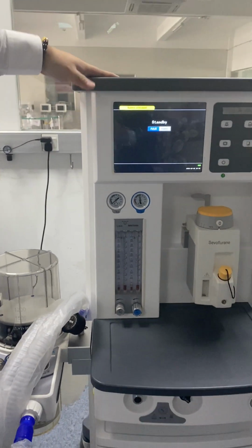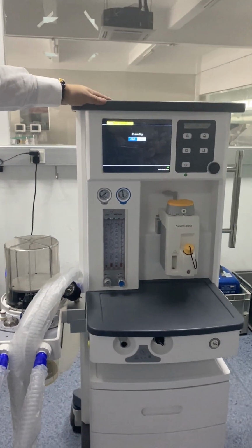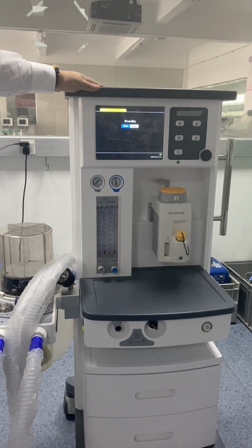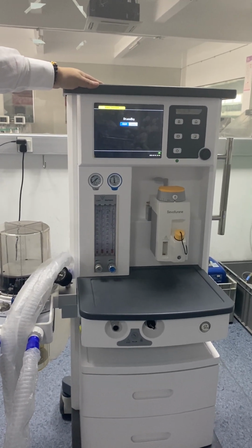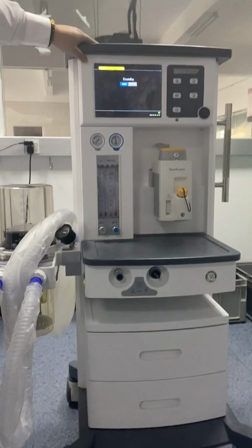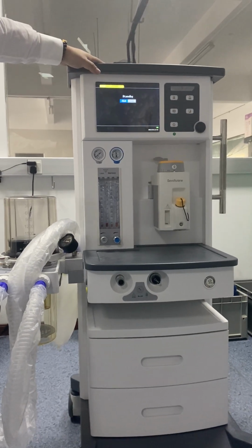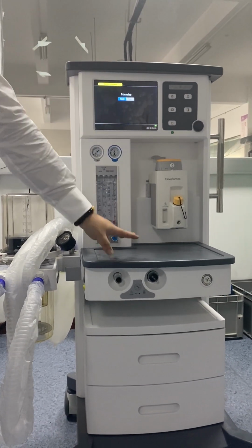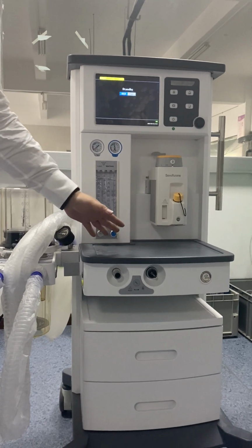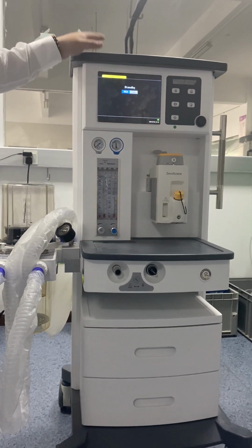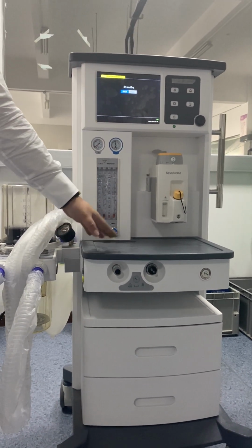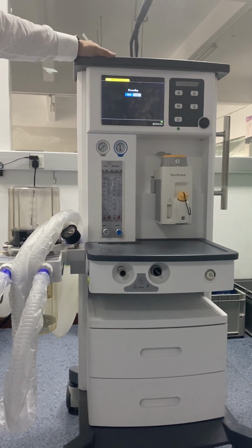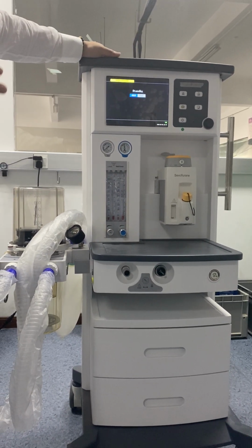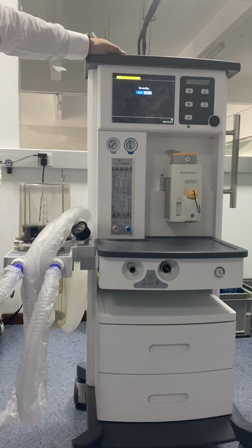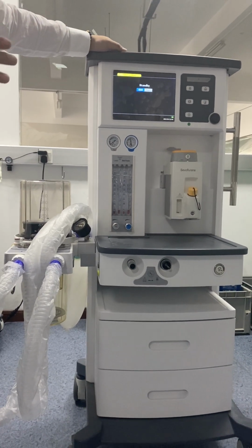Also for this machine, inside the machine, we have a separate design for the gas circuit and the electric circuit. It means when you open this cover, you will only see the electric lines inside. When you open this cover, you will only see the gas tubes. So actually they are in different places. It will ensure that the gas tubes and the electric lines will not cross over. So later, if the machine has any problem, we can find the problem exactly and do the change.